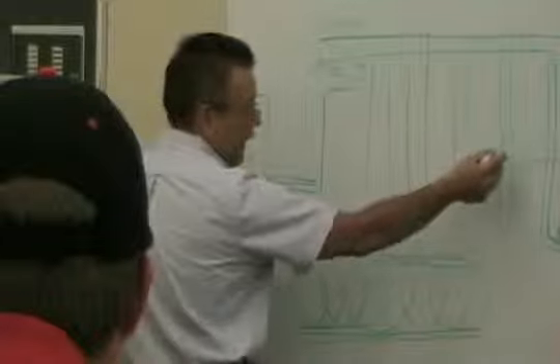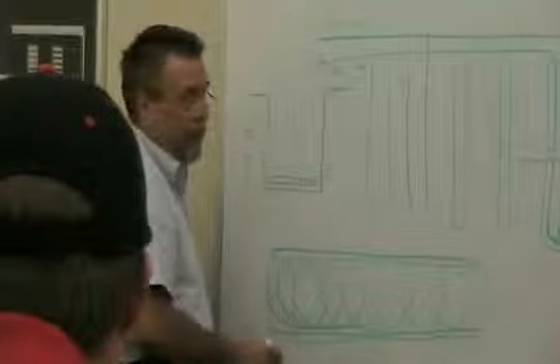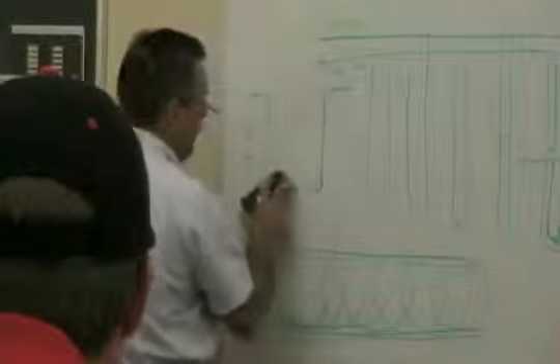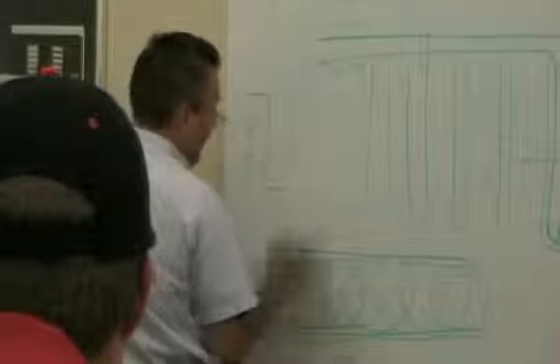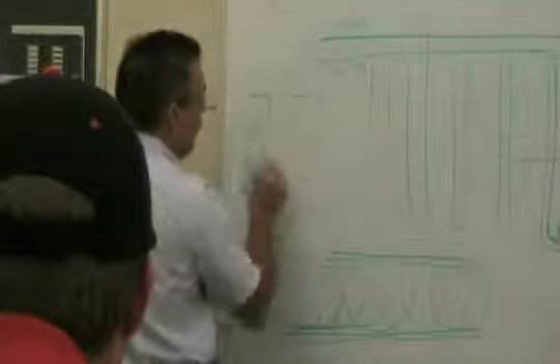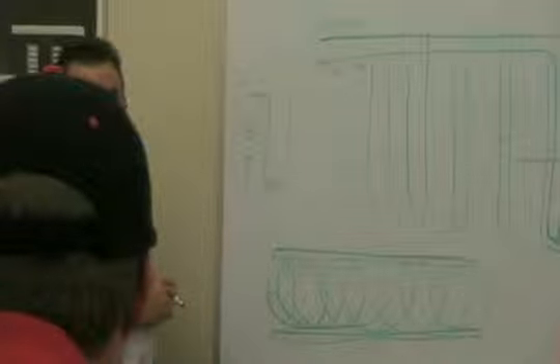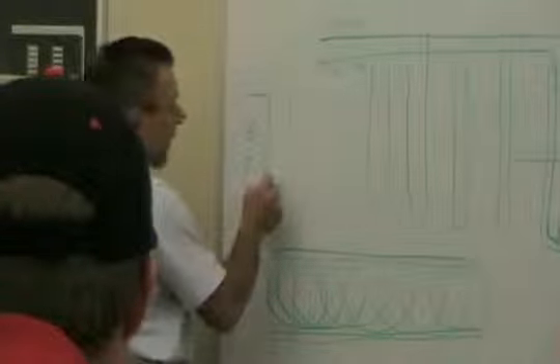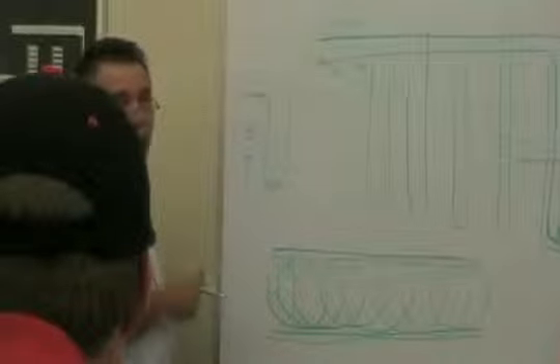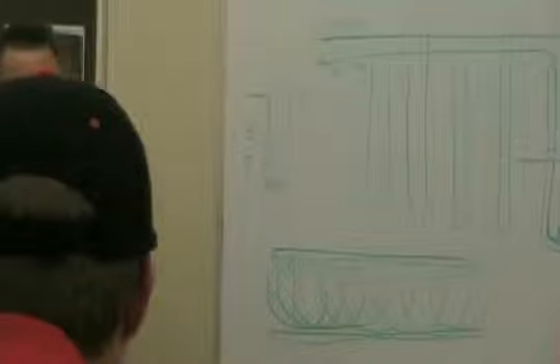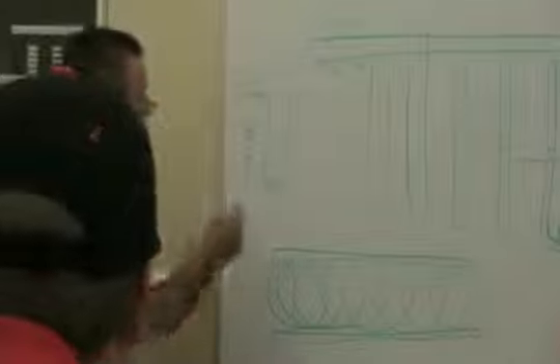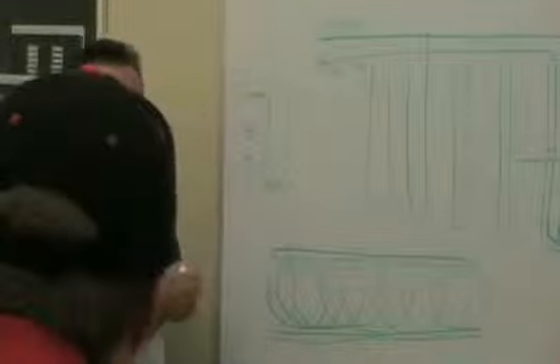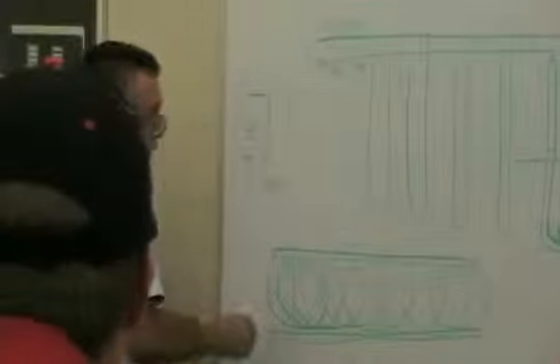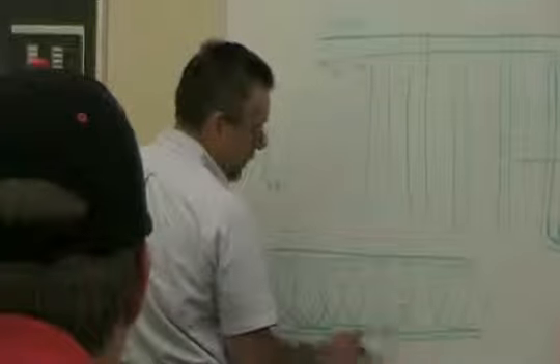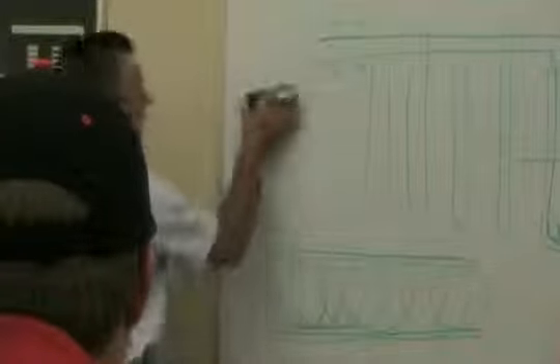This is a vertical well application as well as a horizontal application. I can dig the same ditch and put my supply and return pipe in it in the horizontal application. Generally, your piping lengths might be 60% more in a horizontal application because, again, you're not getting quite the conductivity as in a vertical well. This can be in a horizontal ditch. It can be laid in the bottom of a pond.